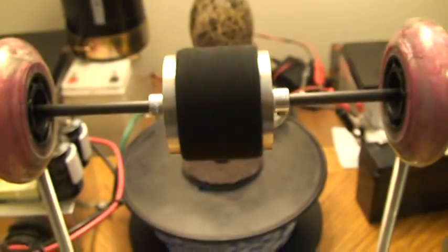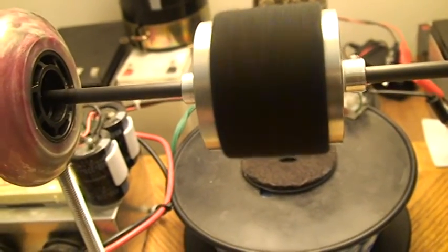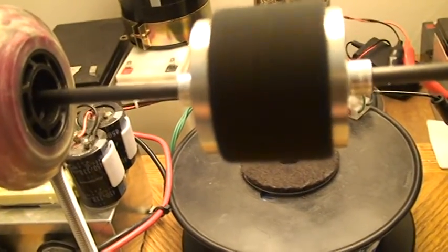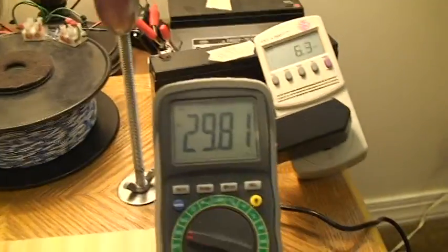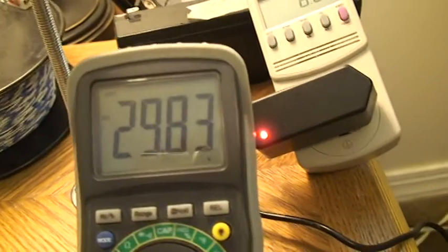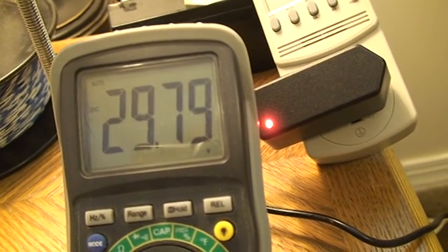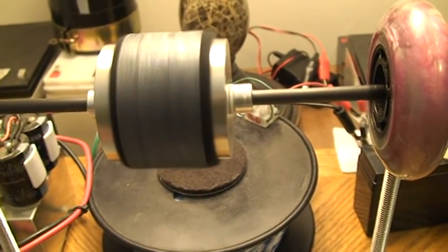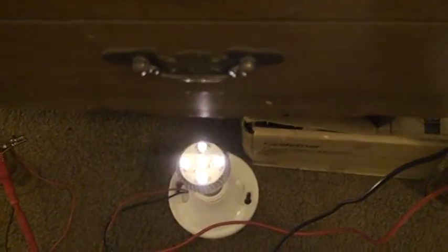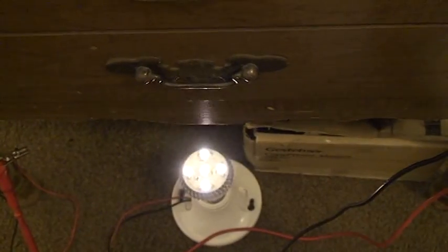There we go. Now the object now is to get this up to about 4,500 RPM. And so we'll do that. And in the meantime, take a look here. Now this voltage, it remains unstable until it gets to about 4,500 RPM. You can see all kinds of crazy things happening here. This thing has to spool up. It gets to 4,500 RPM. By the way, I got my lamp down here. It's flashing right now. It'll go steady once it gets to about 4,500 RPM. That lamp then becomes steady. It doesn't pulse like that.